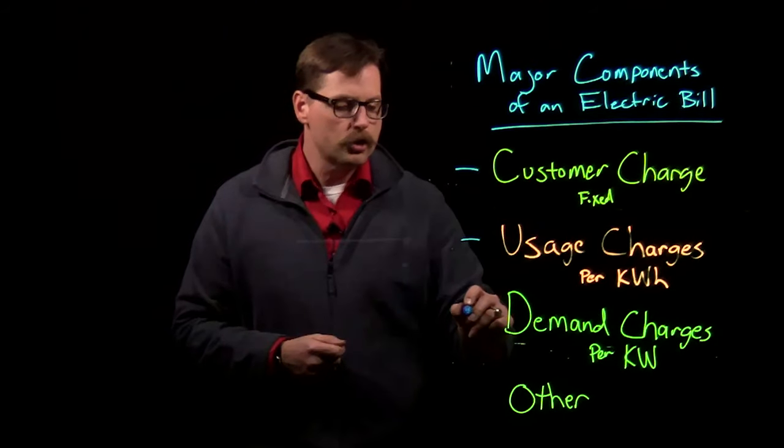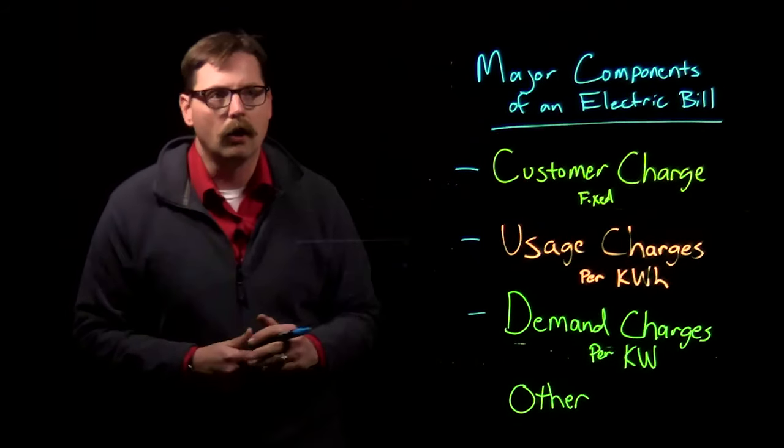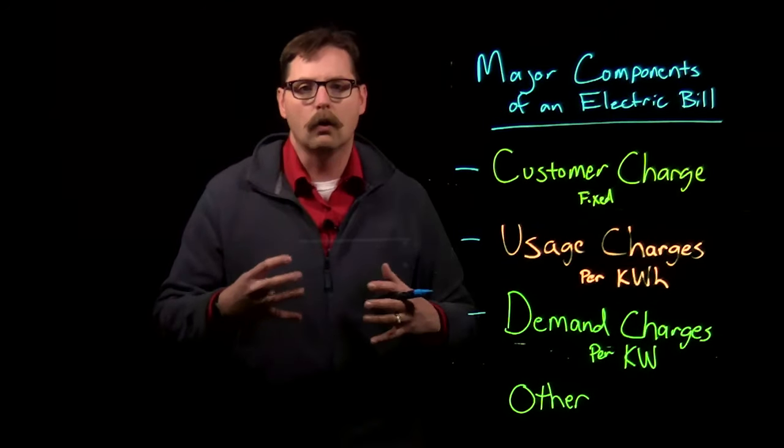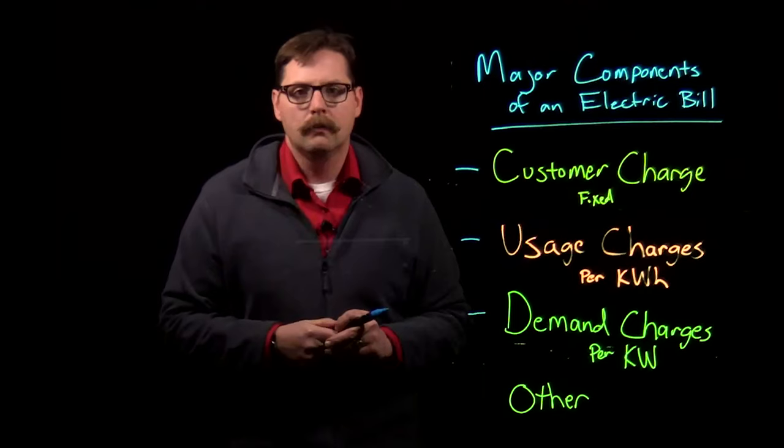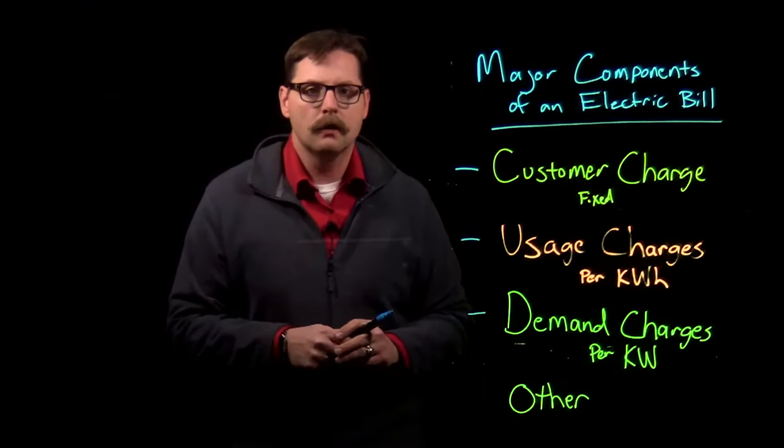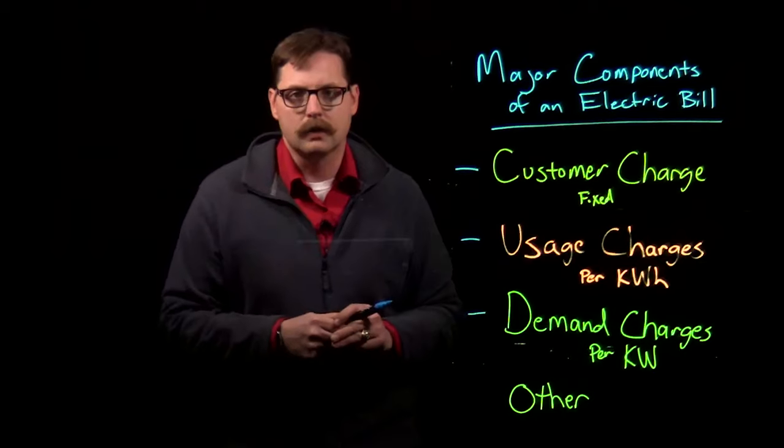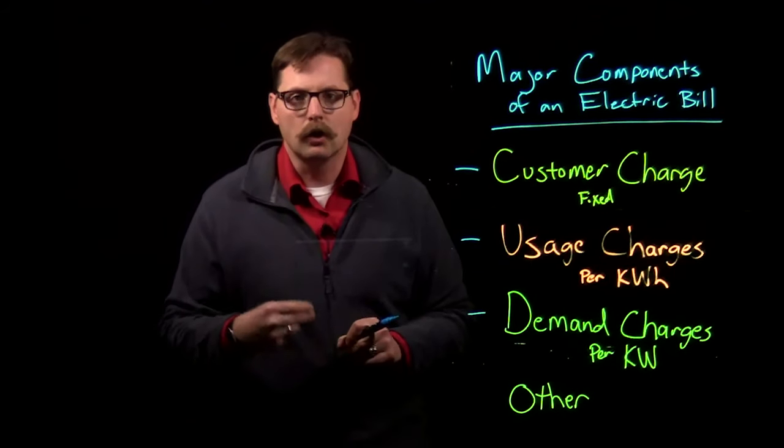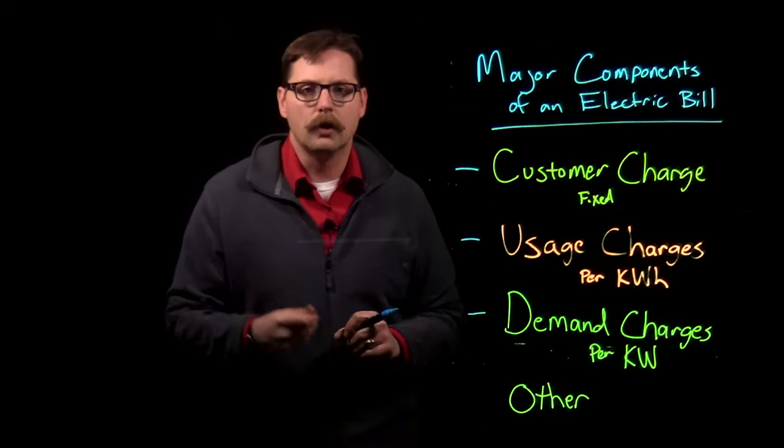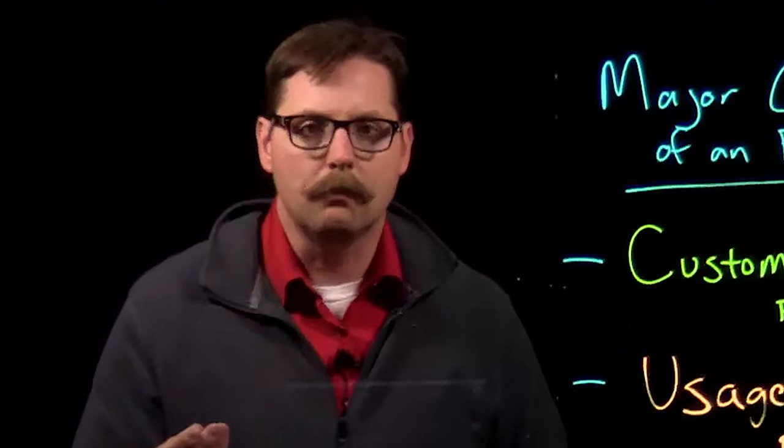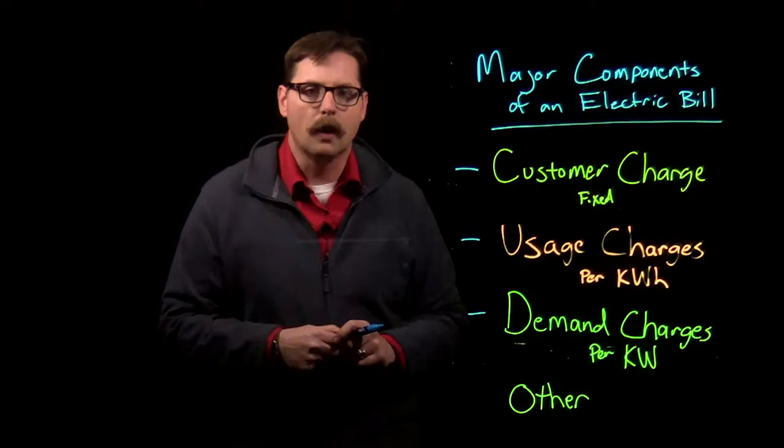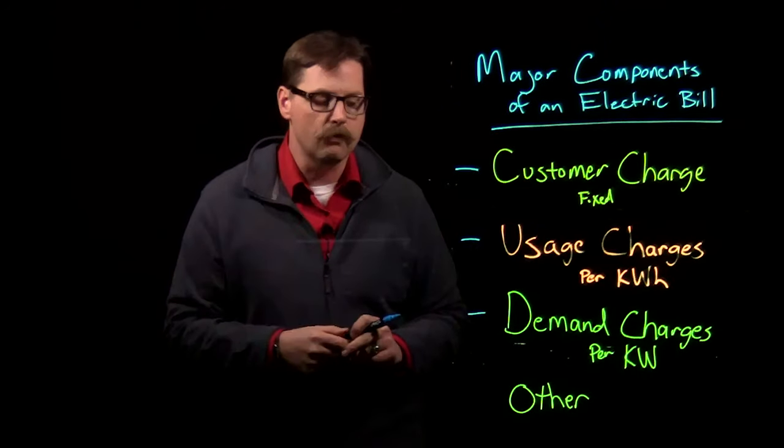The demand charges are charges that are for how much power you are drawing at a peak moment in time for that operation. It's set typically once a year and you're charged that rate for the rest of the year. And that's usually charged per kW or per unit power. So identifying when you set that peak and trying to lower that peak is one operation that could be done to save.